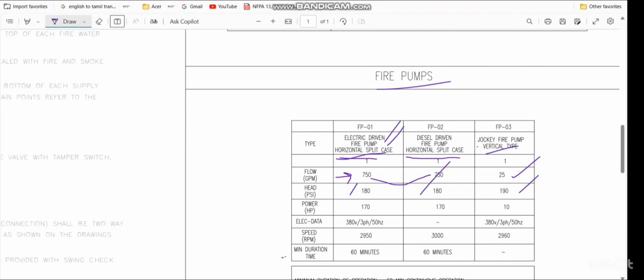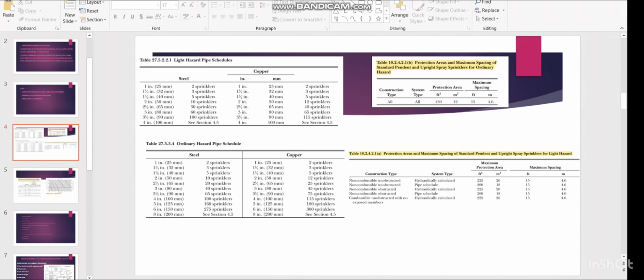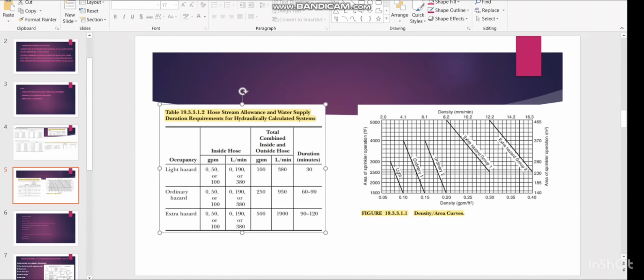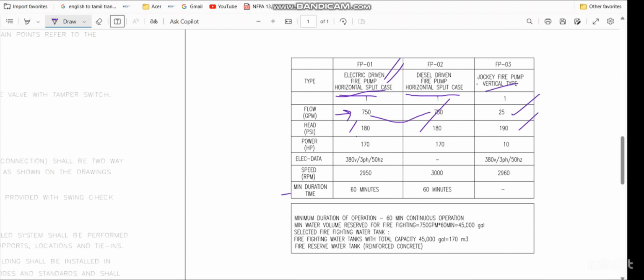So coming to the minimum duration time, we have one NFPA requirement here. For example, if you go to this one, here you can see for the light hazard, ordinary hazard and extra hazard, 3 different values are given. For the ordinary hazard, the water tank duration is 60 to 90 minutes, and the minimum for the light hazard is 30 minutes, extra hazard 90 to 120 minutes. So for this Qatar project, we have followed a minimum duration time of 60 minutes.